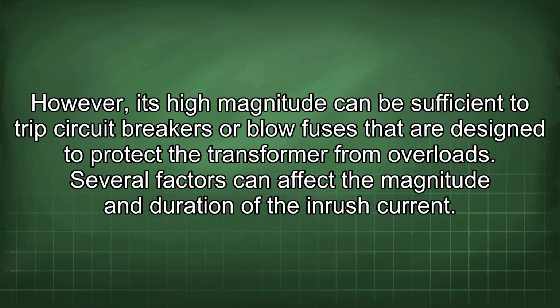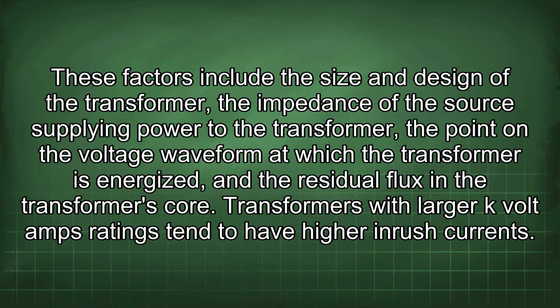However, its high magnitude can be sufficient to trip circuit breakers or blow fuses that are designed to protect the transformer from overloads. Several factors can affect the magnitude and duration of the inrush current. These factors include the size and design of the transformer, the impedance of the source supplying power to the transformer, the point on the voltage waveform at which the transformer is energized, and the residual flux in the transformer's core.